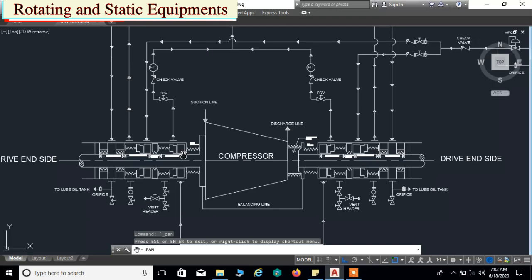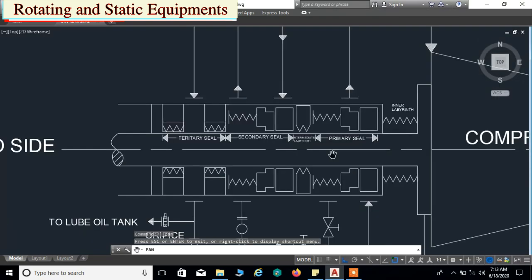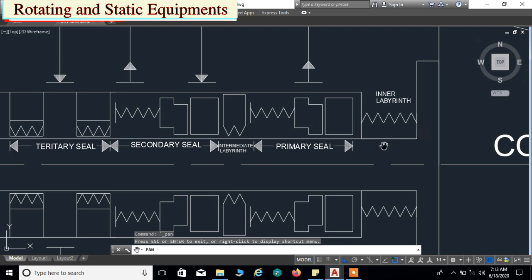Next we will go to the non-drive end side. Similar to the drive end side, from the shaft end we have an inner labyrinth seal. Next to the inner labyrinth seal the dry gas seal unit is started. The first unit is called the primary seal. It consists of a set of seal ring, mating ring, primary sleeve, primary housing, primary retainer, primary static elements, and springs.